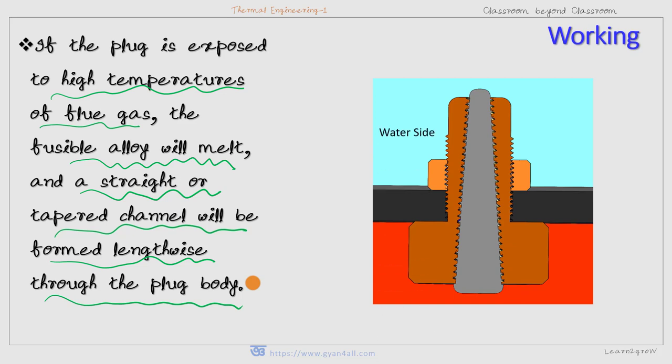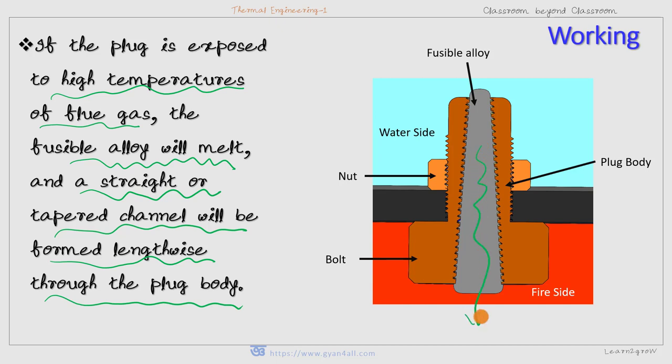Let us see with the help of this diagram. The upper side is the water side and the lower side is the fire side. This is the plug body and this is the fusible alloy, fastened with the help of a nut and bolt. The fusible alloy is threaded in a tapered manner. If the fusible alloy melts, a tapered channel will be created through which steam or water may come down to the combustion chamber and extinguish the fire inside the furnace.